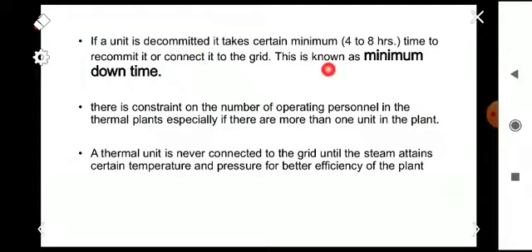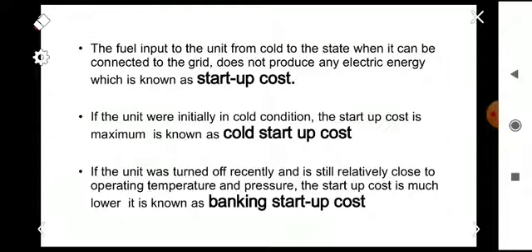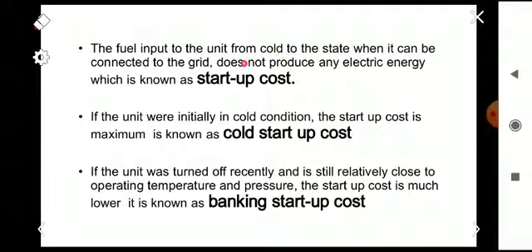If a unit is decommitted — that is, not in operation mode — it takes a certain minimum time, typically 4 to 8 hours, to recommit it or connect it back to the grid. This time is called minimum downtime. There is also a constraint on the number of operating personnel in thermal plants, especially if there are more than one unit. A thermal unit is never connected to the grid until the steam attains a certain temperature and pressure. The fuel input to the unit from cold state to when it can be connected to the grid does not produce any electric energy, which is known as the startup cost.